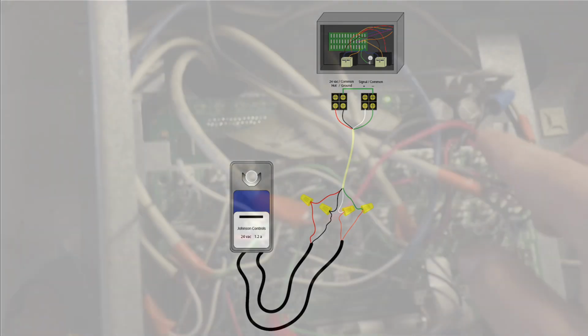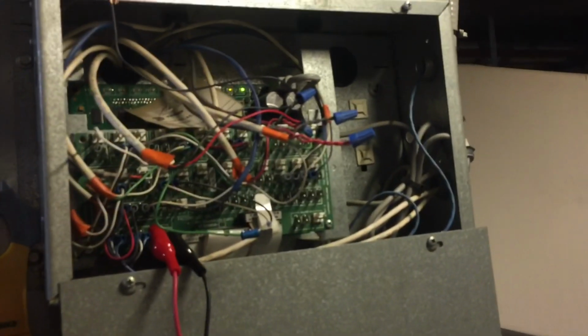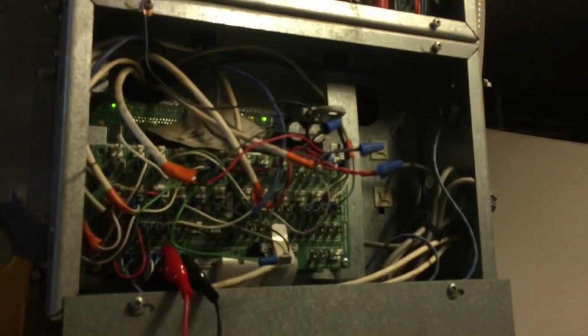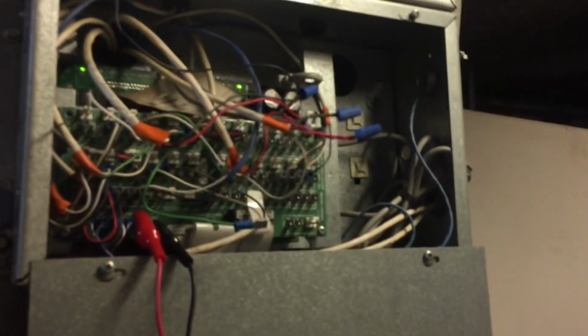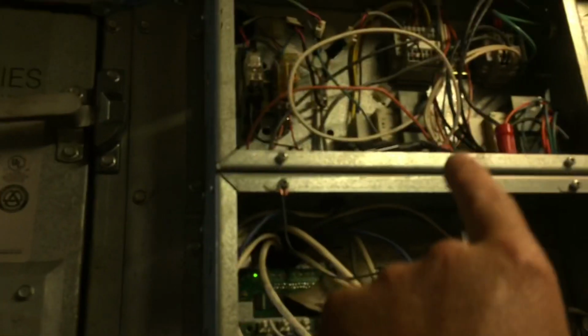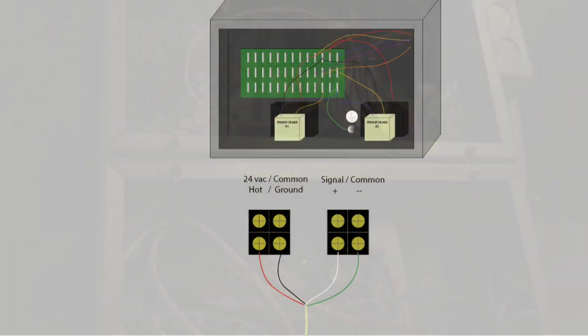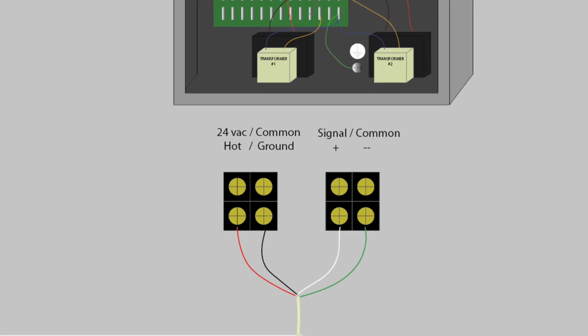There's one here, and then there's one in the back here, these black and red. So I go to each transformer, I check the first one, which my device is not on, and I checked that the ground, or the common, was grounded, and I had continuity between common and ground with the power off. Then I went to the second transformer, which is the one that my device is connected to, and I did the same thing, and I had no ground continuity.